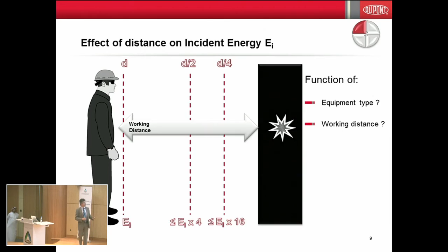The second concept, from the standard IEEE 1584, is the arc flash boundary - the boundary within which a person could receive a second-degree burn from an arc flash incident. Once someone crosses the boundary, they have to be protected, because in case of an event they could be exposed and receive a second-degree burn.